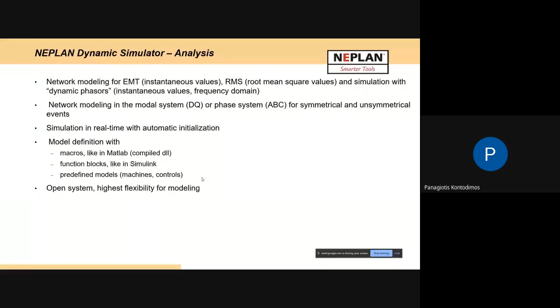What we also need for dynamic simulation very often is the controller. For load flow calculation, I don't need to know the AVR controller transfer function, or the power system stabilizer, or the turbine control—for example, if we have a hydro generator, how the turbine is opening or closing the water flow. But when doing dynamic simulation, we need this information, and we have a very user-friendly way to include it. We can make the controller model with block diagrams, like in Simulink, or we can use macros to define the controllers using equations.